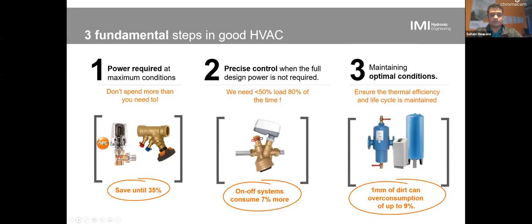And the third one is looking even further out in the system, where we want to make sure we have the right static pressure, the proper degassing, air and dirt separators and all that, because of those pipes, the pictures we looked at earlier, if you have 1 millimeter of dirt on your pipes, that can result in up to 9% overconsumption in pumping energy. So it's important we take a look at the system overall and understand what we need to do to make sure everything is working, not just working, but working efficiently, right?